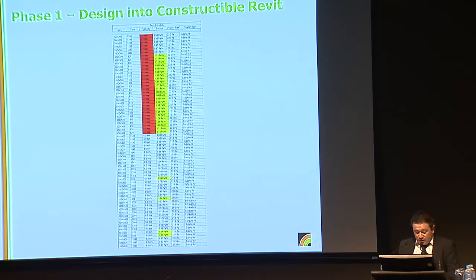This is done with the design information using conditional formulas in schedules, which highlight areas of concern. So here we've just punched in to highlight all the ducts that have a velocity higher than 6 metres a second and friction greater than 1 Pascal per metre. So there, that's the velocity, the duct velocity, and the yellow one being the friction.